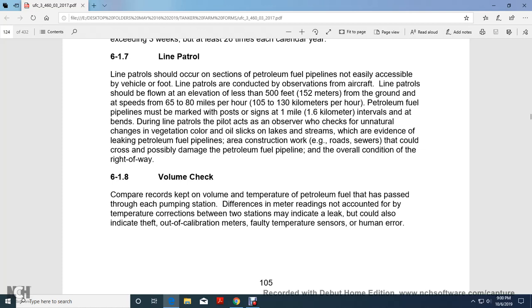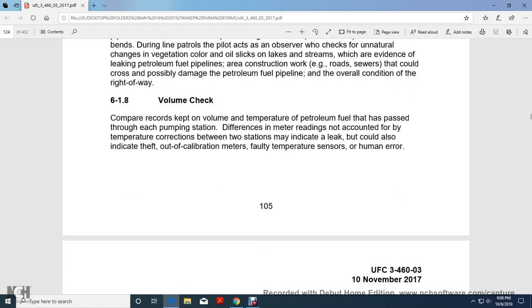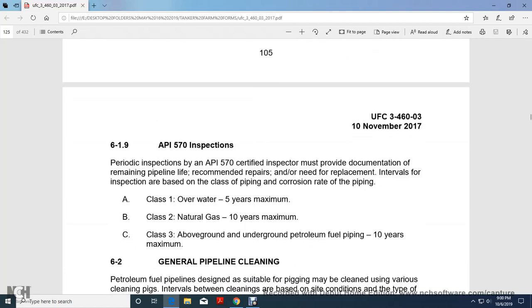Areas could be crossed, possibly damaging the petroleum fuel pipeline; check the overall condition of the right of way. Volume check: compare the record of the volume, corrected for temperature, of the petroleum fuel that has passed through each pump station. A difference in the meter readings, not accounted for by the temperature correction, between the two stations may indicate a leak, but may also indicate out of calibration meters, faulty temperature sensors, or human error.